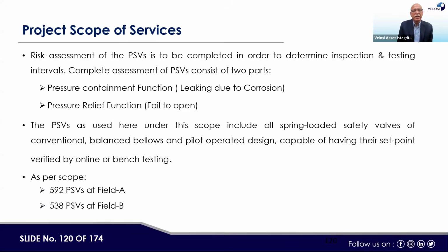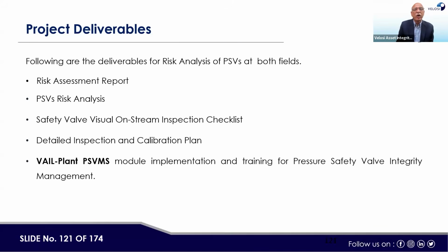There are basically 592 PSVs at field A and 538 PSVs at field B. This is the total number of PSVs. Following are the deliverables for risk analysis of the PSVs at both fields: risk assessment report, PSVs risk analysis, safety valve visual on-stream inspection checklist, detailed inspection and calibration plan, and then VAIL-Plant PSVMS module implementation and training for pressure safety valve integrity management.